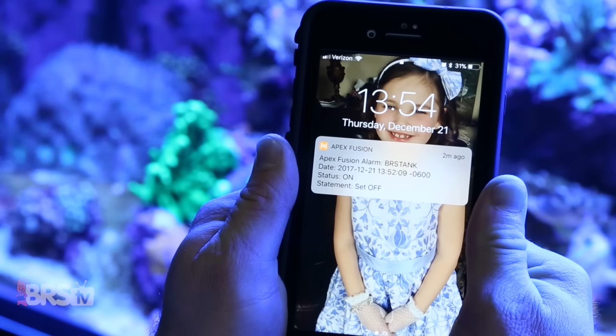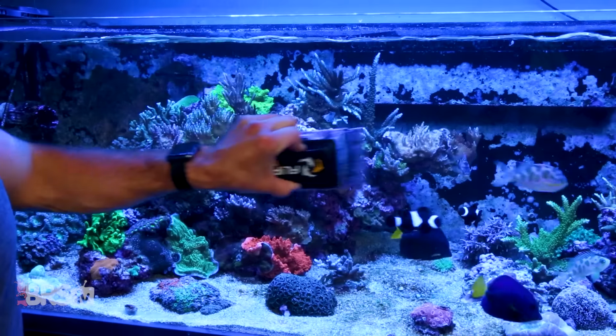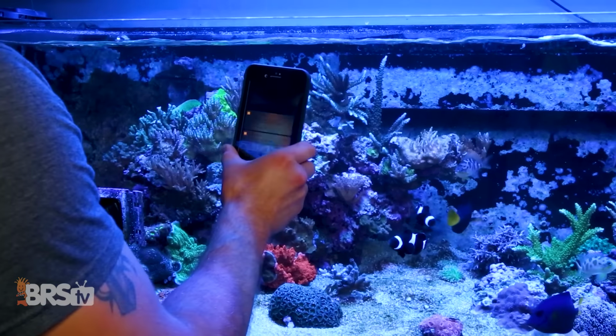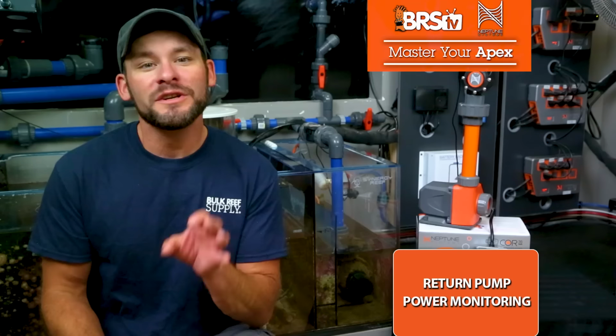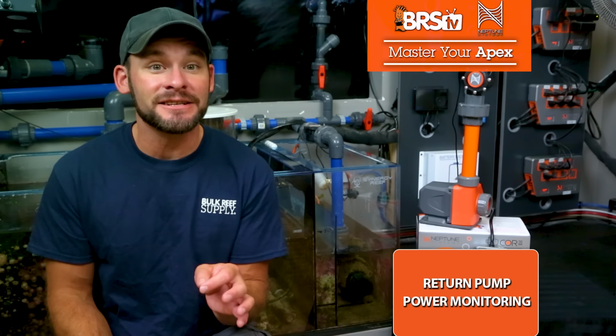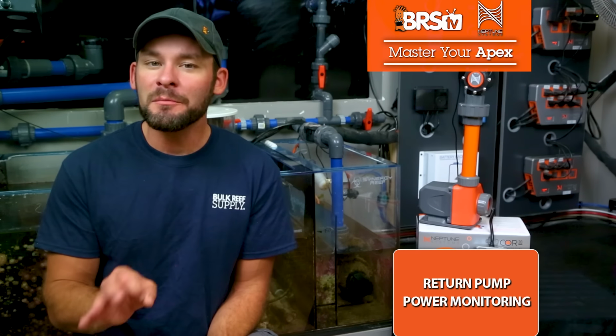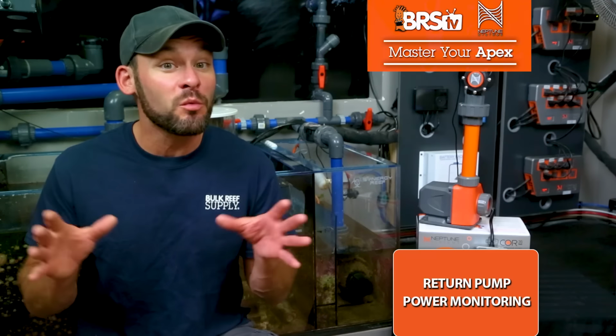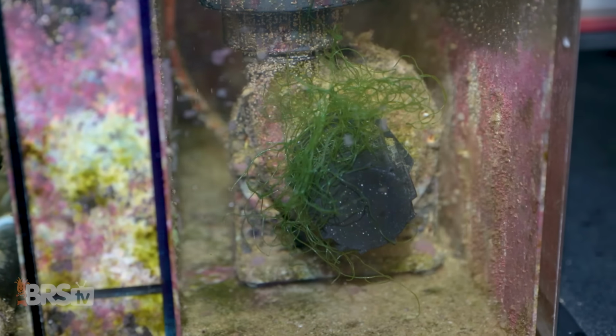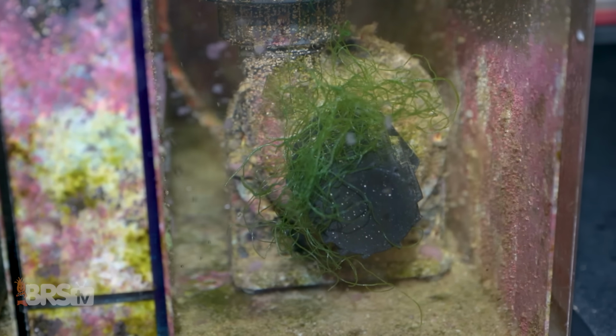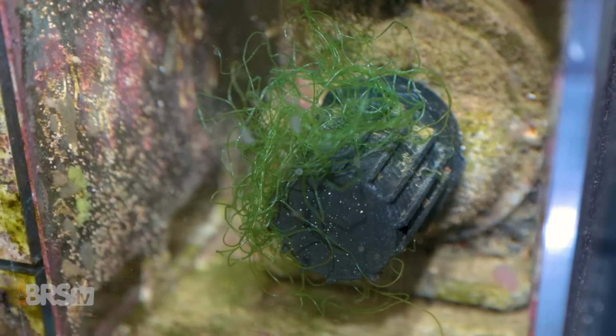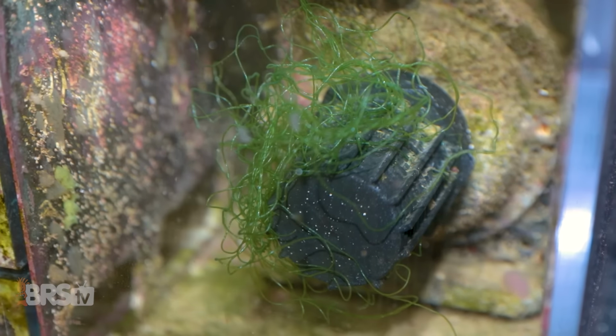Using power monitoring, not only can you get emails, alerts, and notifications if your return pump fails to draw power at all, which substantially gives you an advantage to respond immediately, but power monitoring can also provide you with a window into your pump's performance, like it's still running but drawing less power than normal, which tells you that it might be clogged, obstructed, or that it's time to be cleaned.